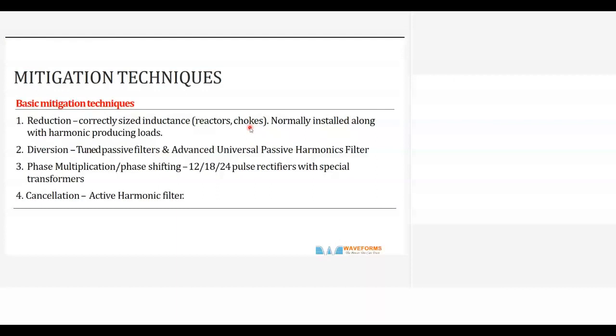So it does reduce harmonics by 20 to 30%, but they do not mitigate them totally. And they can reduce the peak currents also. So that's all a reactor or choke can do. But there's another technique called diversion, which is to tune the passive filter to create a low impedance path for that particular harmonic and divert it. And then we have something called the advanced universal passive harmonic filter, which I will come to later. But the technique is diversion.